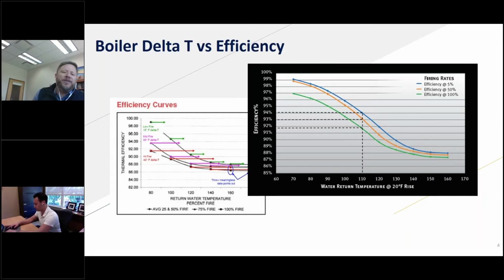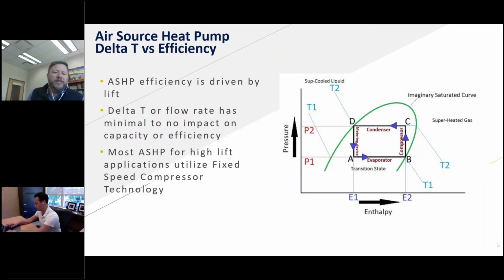So as we think about this, boiler technology is different than air source heat pump technology, and what drives efficiency ends up being something different. If we're comparing what we have traditionally done versus what we will be doing moving forward, this is one place where we start to see a little bit of a nuance or a change. An air source heat pump's efficiency really is not driven by a delta T or a flow rate. Okay.